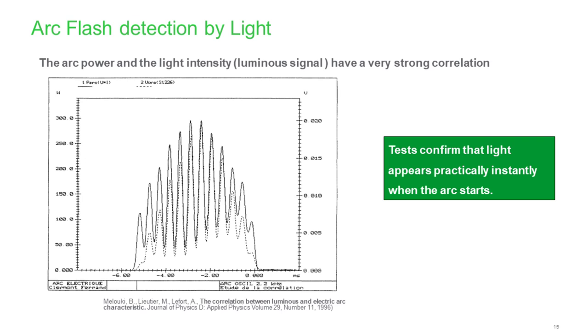Another way to detect the arc is by using light. Testing proves that light appears practically instantly when the arc starts. The solid line shows the energy of the arc and the dotted line shows light intensity — they appear at almost the same time. So light is definitely a faster way to detect arc flash.